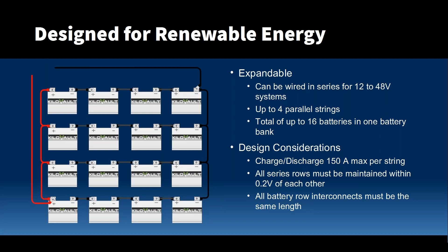And in terms of what is really most appealing about these batteries, I've already touched on the high charge and discharge current, especially in residential storage applications. They can also handle higher surges from larger inverters, 500 amps for 3 seconds, for example, which in a stacked Radian or XW system could very well be a possibility. And when we're talking about building this battery bank up to 16 units in total, that's upwards of almost 60 kilowatt hours for the larger model, which is a pretty significant amount of storage for residential systems.